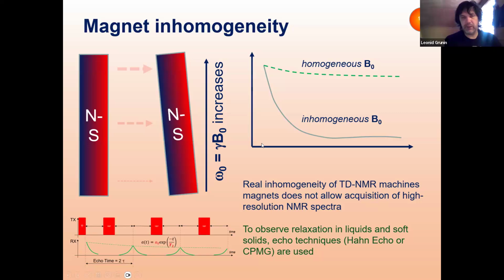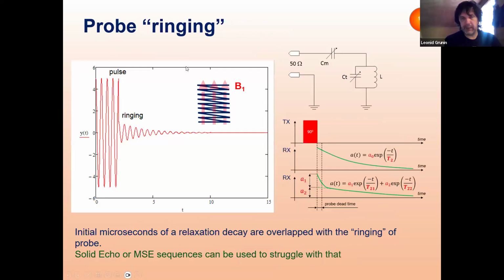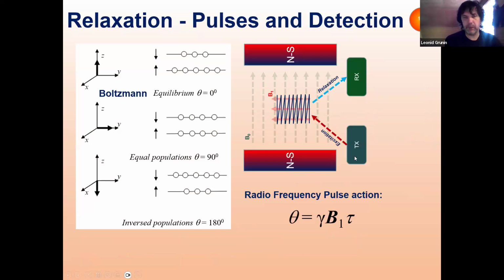So let's say these are the two main drawbacks. The other challenge in time domain NMR of solids is the so-called ringing time of the probe. In this structure we have the transmitter, which excites, the receiver, which receives the relaxation signal, and the coil. Normally the transmitter pulse must be very strong, a few kilovolts across the coil, and when we detect the signal, it is a few microvolts. So the response is much lower.